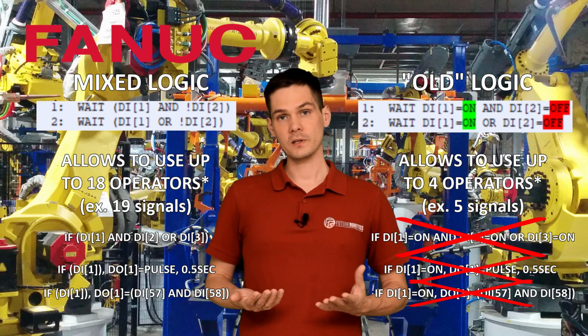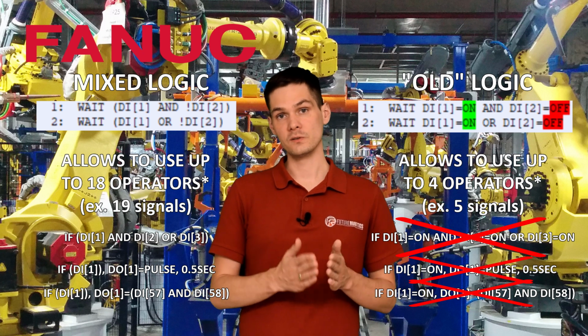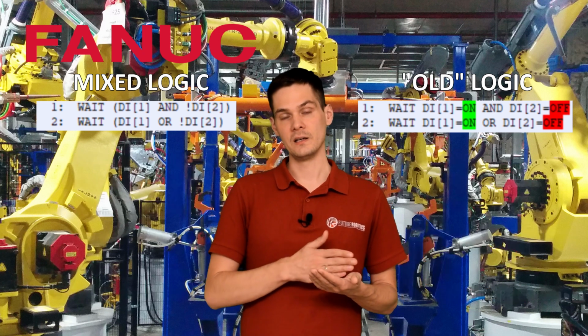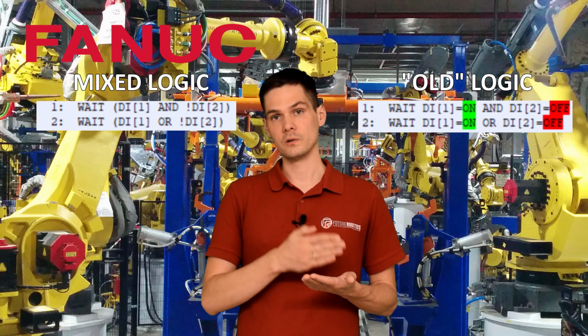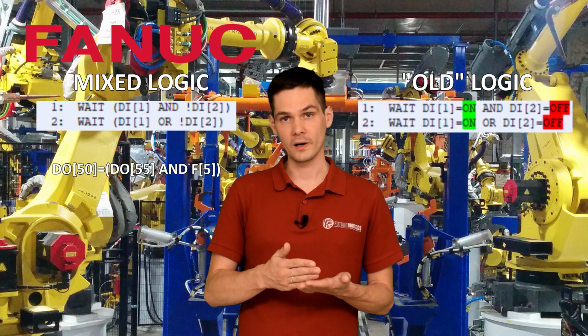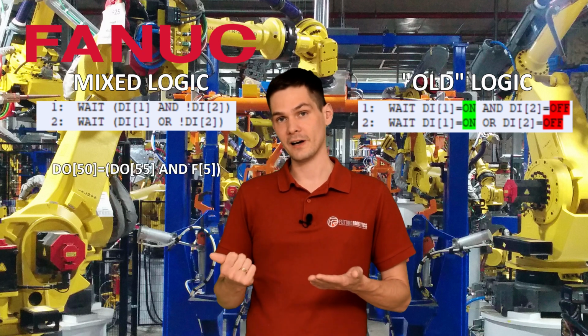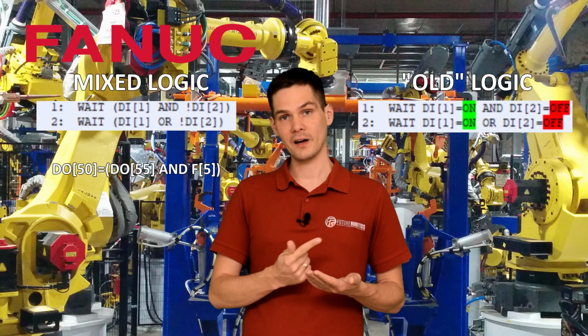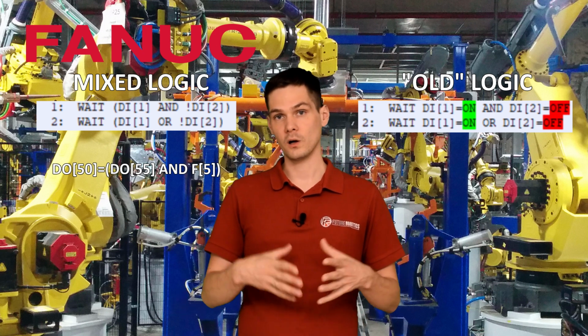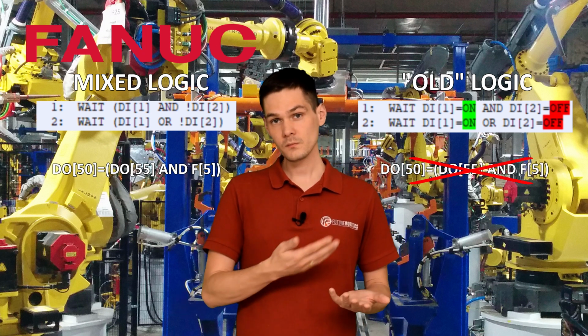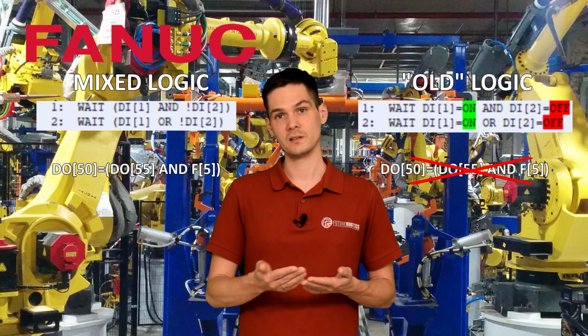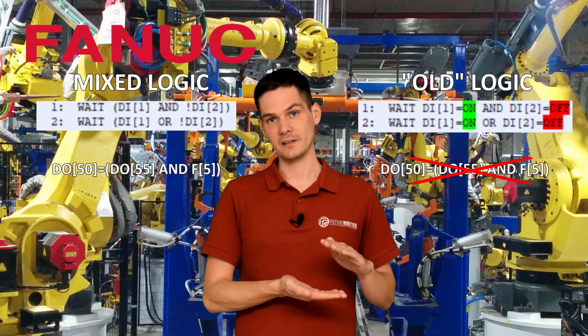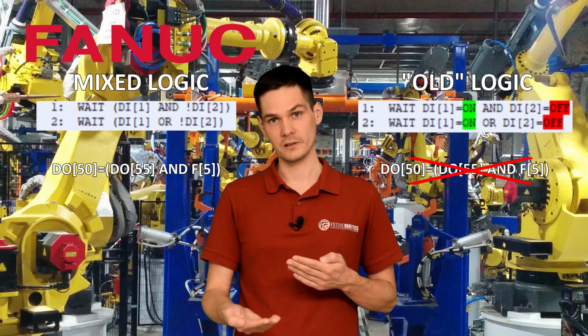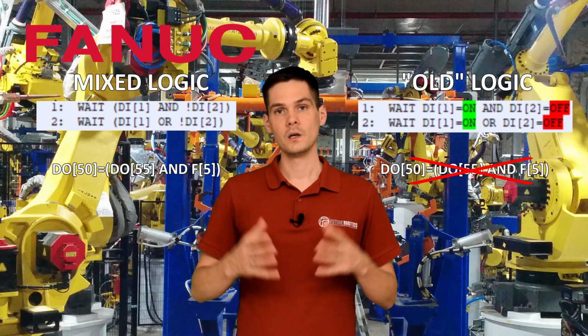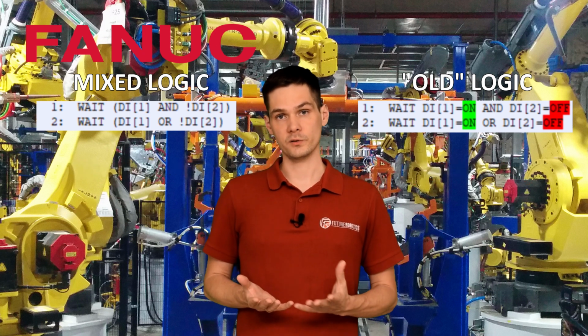So for example, you can turn on a DO using many statements. You will say, I want to turn on DO 50, for example, when DO 55 is on, flag 5 is on, and so on and so on. With the old logic, it's not possible. Over there, you would probably need to create an if statement, and inside the if, then you will make your output on. What else about those logics?